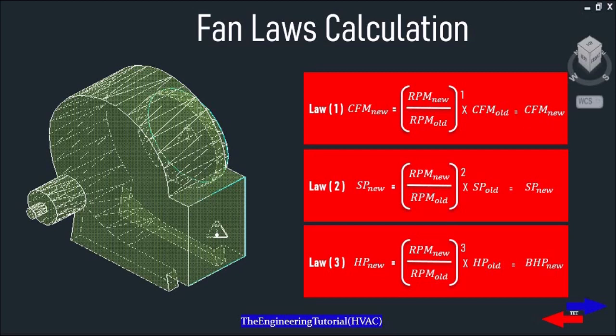The second fan law is used to determine the static pressure as the speed of the fan changes. A change in fan speed has a significant impact on pressure, and that change is calculated according to the square of the speed ratio. Fan Law 2: Static Pressure new equals (RPM new divided by RPM old) squared, multiplied by Static Pressure old, which gives us Static Pressure new.